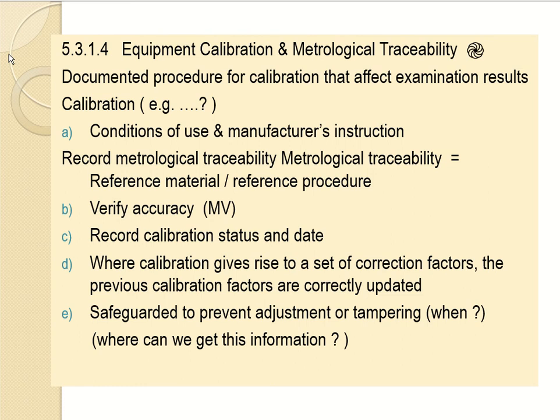Okay, under clause 5.3.1.4, equipment calibration and metrological traceability, there should be documented procedure for calibration that affects examination results. Usually the calibration included here is the calibration of the test, and it should cover the condition of use and manufacturer instruction, which is recorded metrological traceability, that is traceability to reference material or reference procedure. This information we can get from the manufacturer. Should have a procedure for verifying accuracy, done by the manufacturer, or we can do it by ourselves. And this one I will cover in my next lecture.